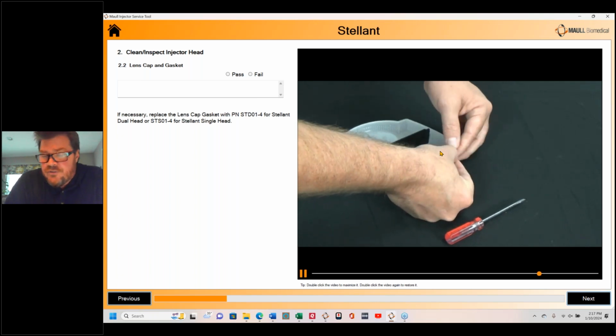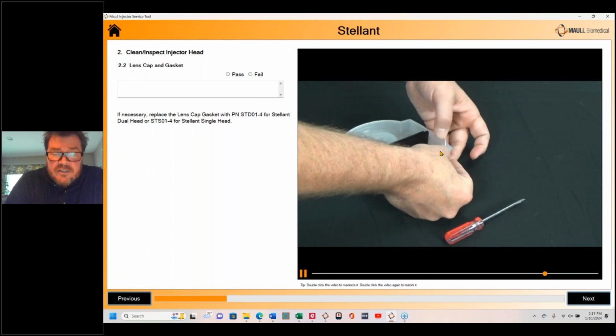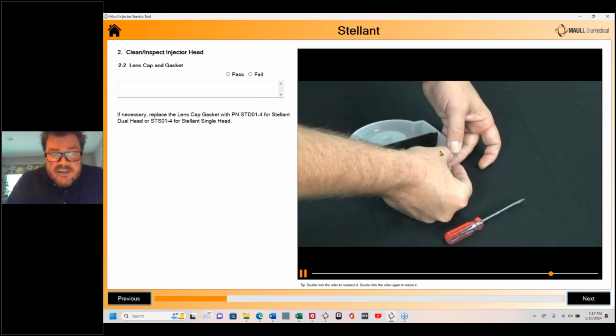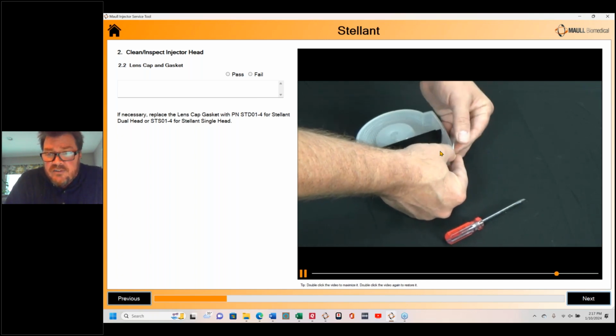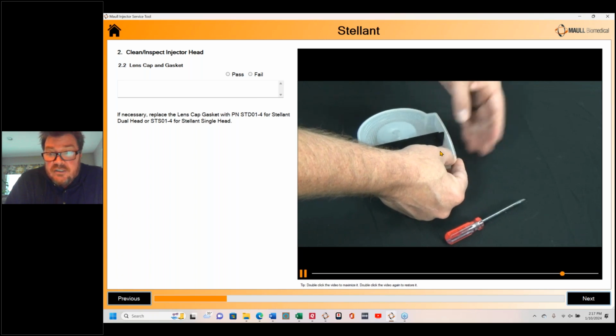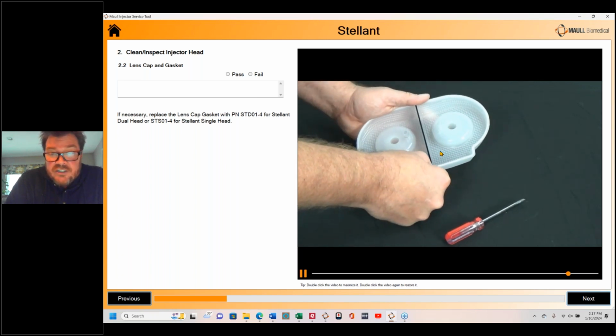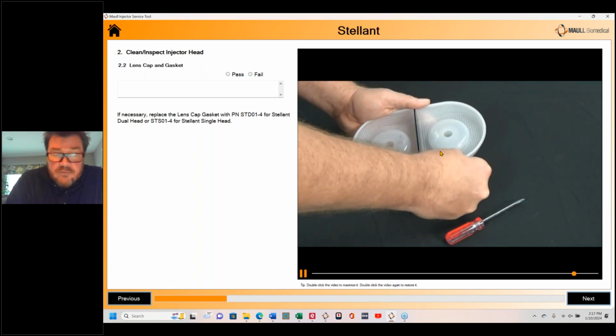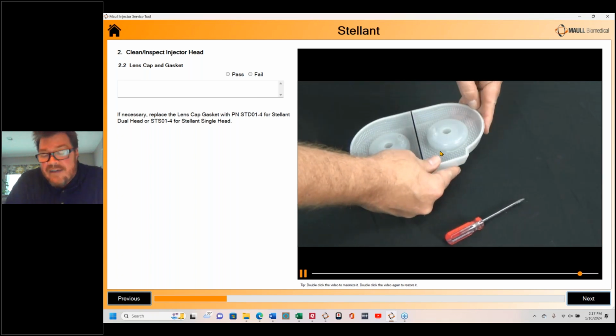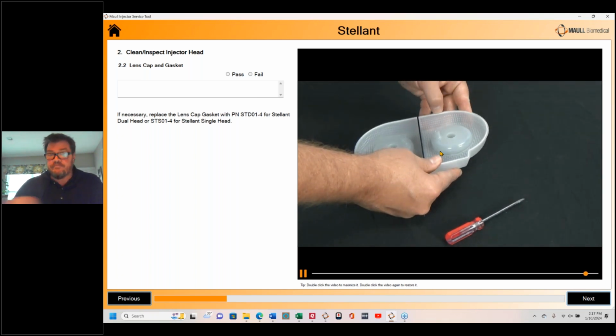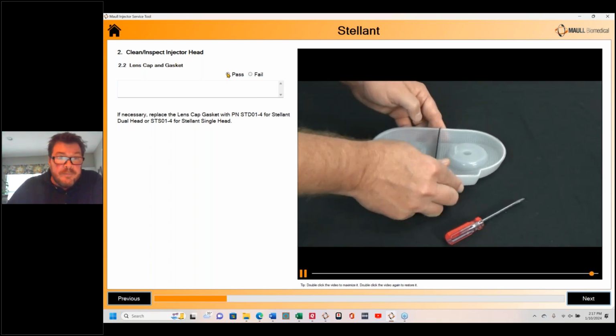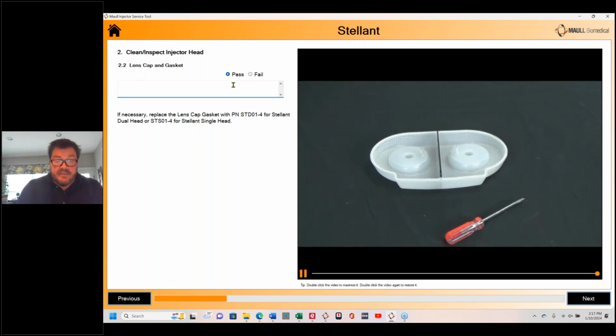And that's what I tell the students. Most of the time, the gaskets on these contrast injectors, and it's not just the Stellant here, pretty much every model, if you remove the gasket and it just needs cleaned off and it's still in good condition, you can just put the gasket back on. The gaskets on these injectors don't have to be replaced on an annual basis. And we're going to put pass, and just for giggles, we'll say replaced gasket.